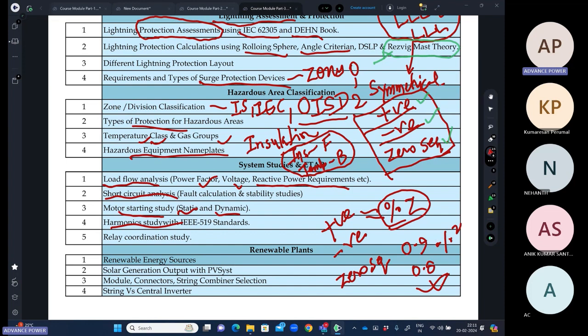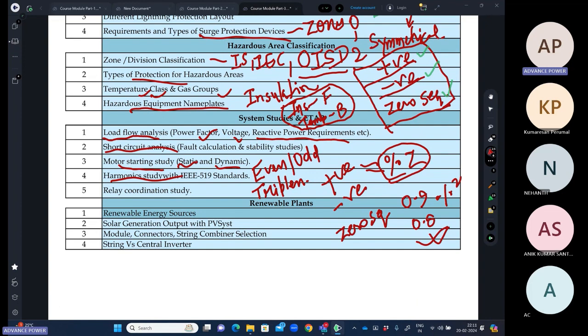We'll discuss about the harmonics. Harmonics, if you broadly bifurcate, we say even order and odd order harmonics. Further, when you bifurcate it, we have the third order or triplen harmonics. In detail also, when there is a fault in the system, then also we say we have positive sequence harmonic, we have the negative sequence harmonic, we have the zero sequence harmonics also.